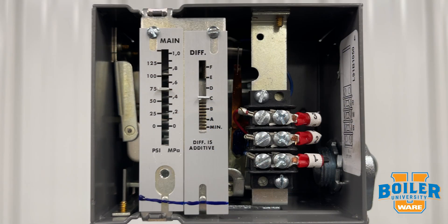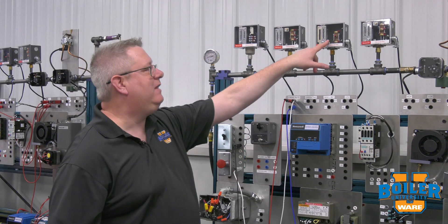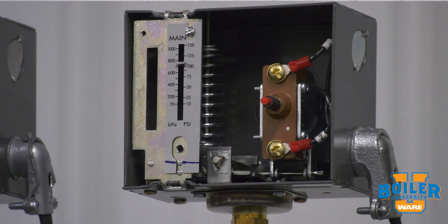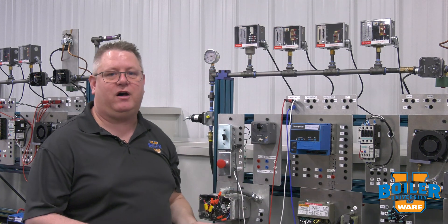If we take the cover off and look at it, we can see it doesn't have a switch mechanism like the other devices. Our high limit is easy to recognize because it has a manual reset button. On the newer mercury-free styles that's on the front, and on the older mercury styles it was frequently on the top.